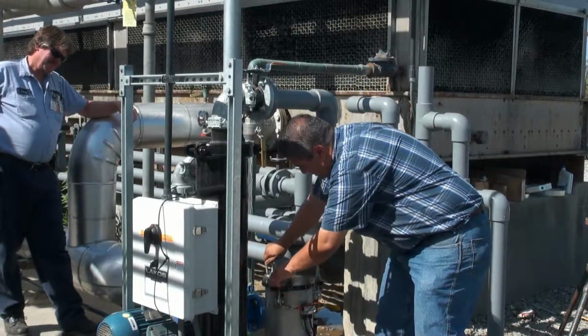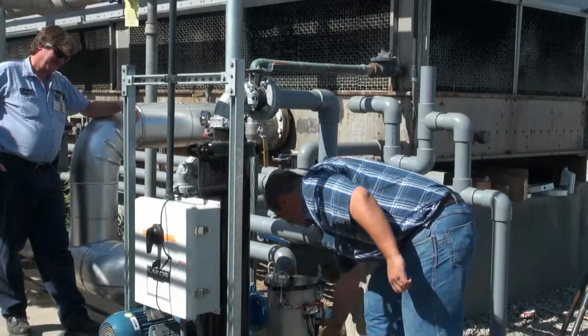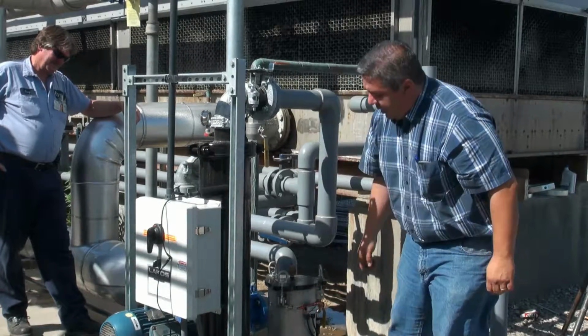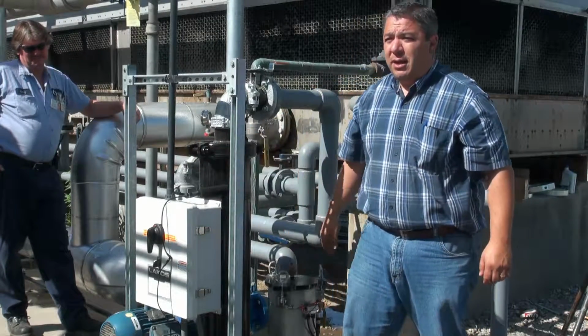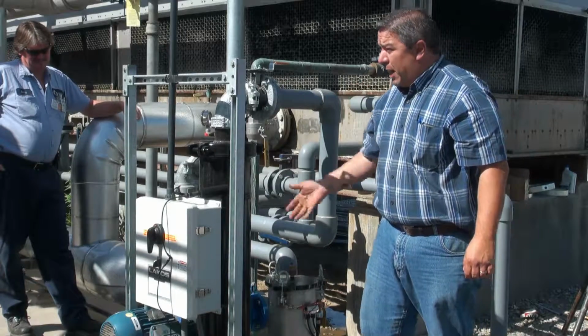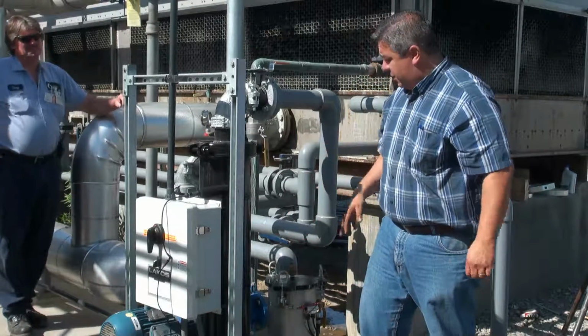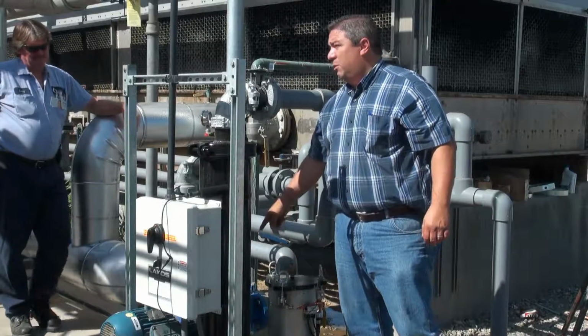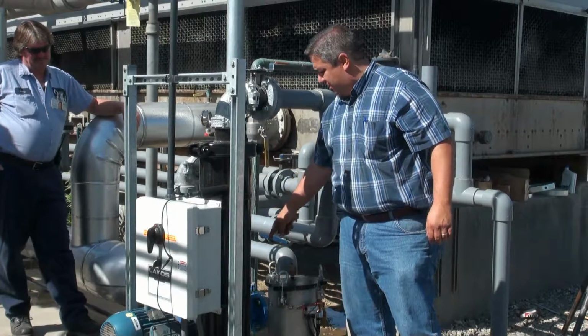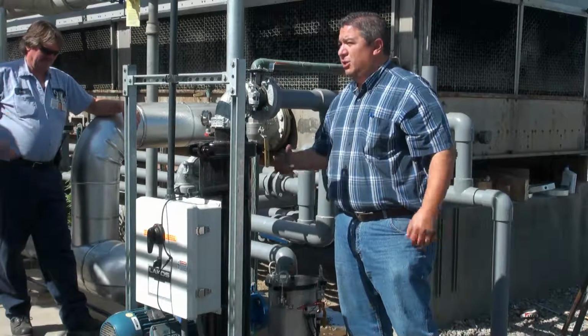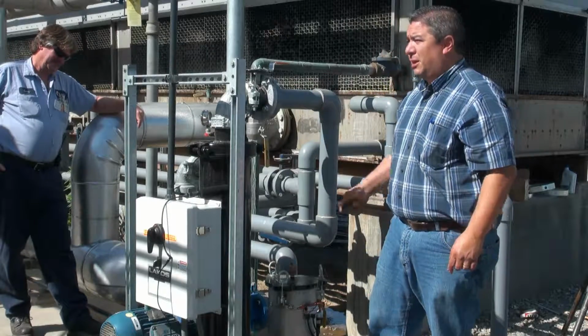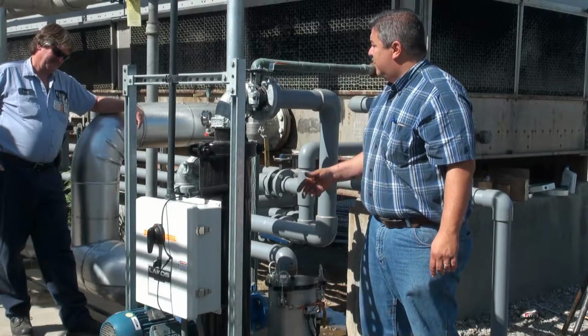Always remember, once you're done, turn both valves back on so the water can flow, then turn it on and you're on your way. On an annual PM, turn it off and do the same thing, but you can also remove the basket strainer. Same deal, take the two nuts and bolts off, it's just a little metal strainer like the ones at the pumps. It comes out, clean it out, and put it back in.